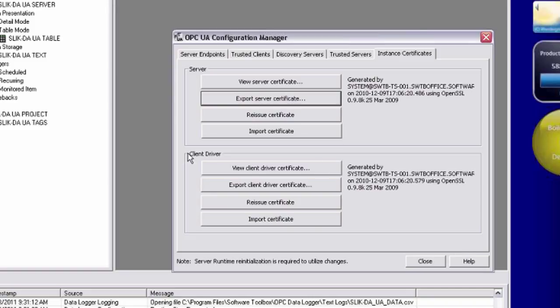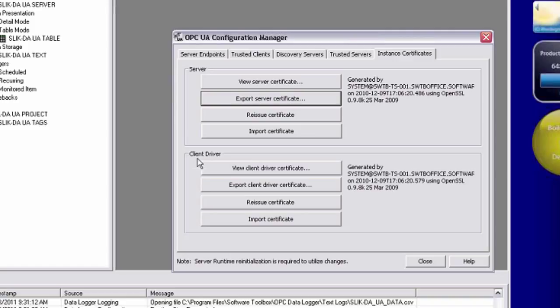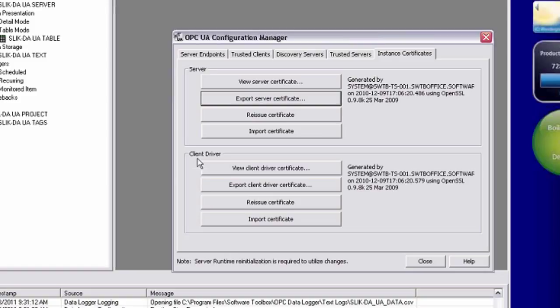Now notice the UA settings are also administered here for the top server OPC UA client driver, which Renee mentioned. I'm not going to be covering that specifically in this demo. The UA client driver makes it possible to tunnel data from a remote top server using that OPC UA interface. It allows the client driver to connect to the UA server interface on a remote top server. And then you can expose the data from that remote top server via DDE, SuiteLink, OPC DA, right on the local machine. So that avoids DCOM as well for clients that don't support natively OPC UA.